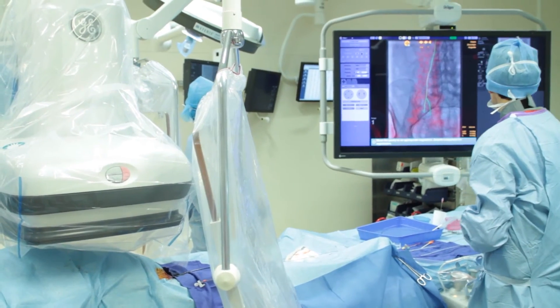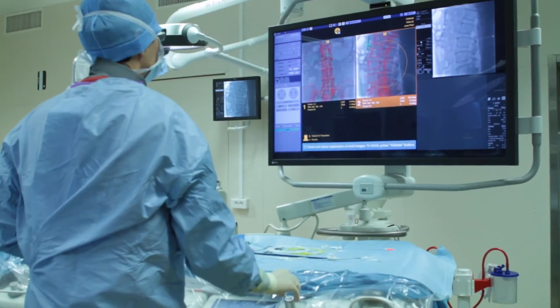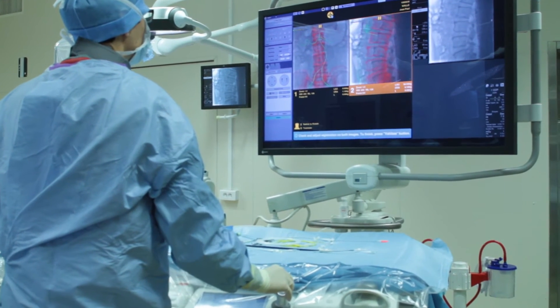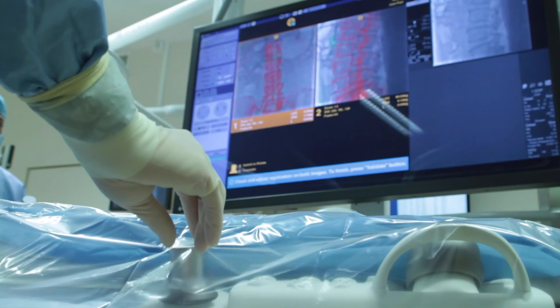What's also very interesting about the new Fusion software is the bi-view mode. We register one fluoroscopic image and then another one with a very different angulation, and we have both views together on the large display monitor. We can then register the pre-op CT image on top of the fluoroscopic image using translation and rotation, looking at both fluoroscopic views. It's very fast, very user friendly, and actually very accurate.